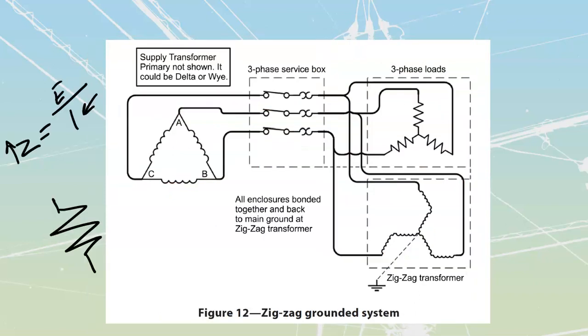There is a note as well at the very bottom of your page 23 that talks about using a grounded Y winding in place of the zigzag winding. It is impossible to use a grounded Y winding. I know we get this question pretty much every class, where somebody is going to ask if we could just use a Y. If I was to take a Y across, an actual true Y over here, just lining these up with the actual lines.